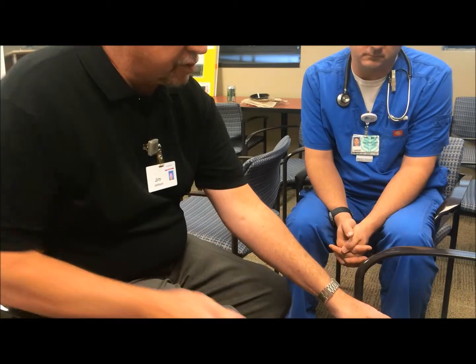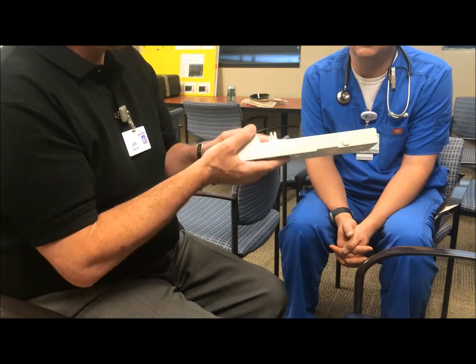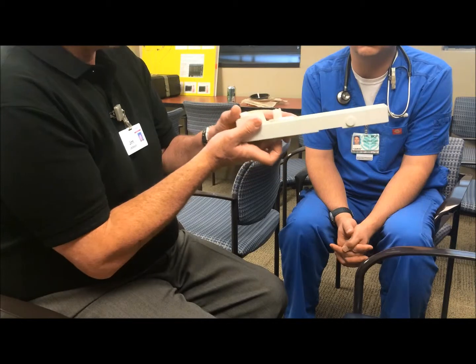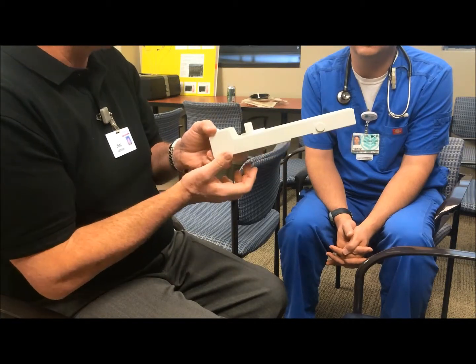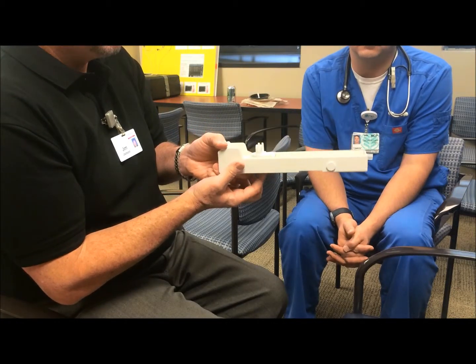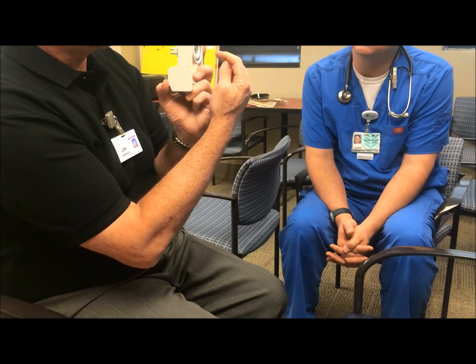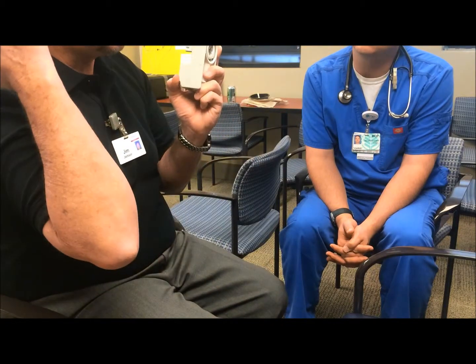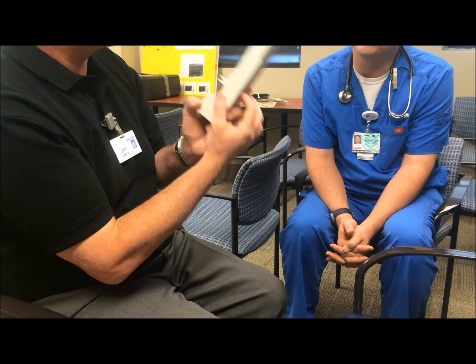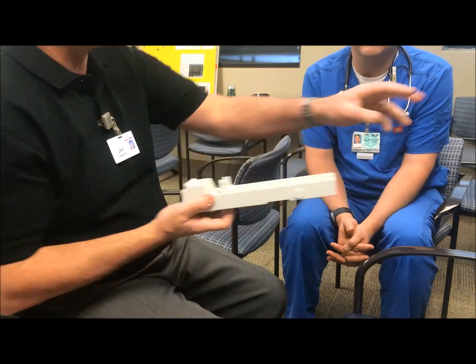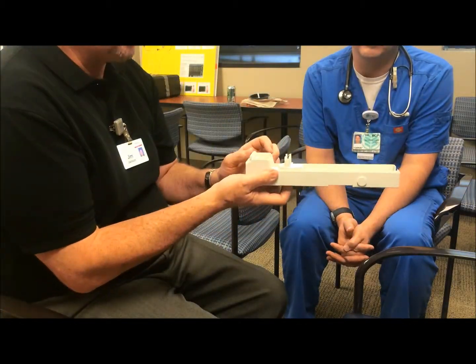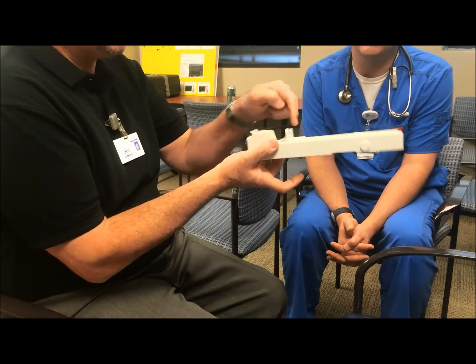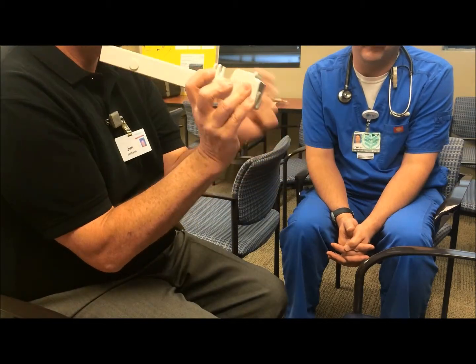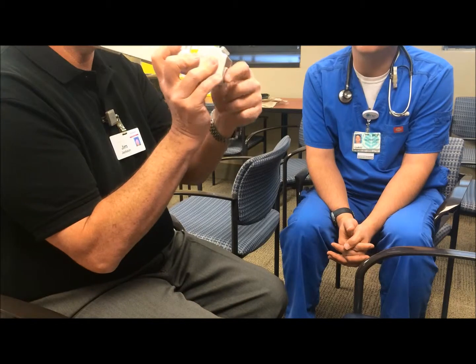So it goes through and then goes in here, and then, kind of like the old IPPB mushroom valves in terms of principle, when the ventilator delivers a breath, there's a metal stem in there that comes up and closes that valve so the patient gets the breath. Then when this is released, gas goes through here, up a tower, and then out.